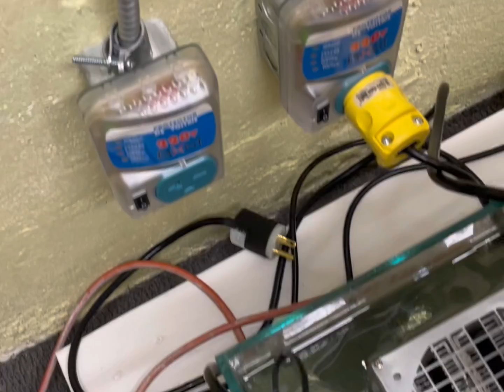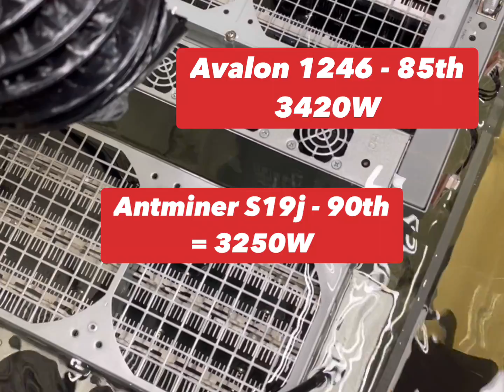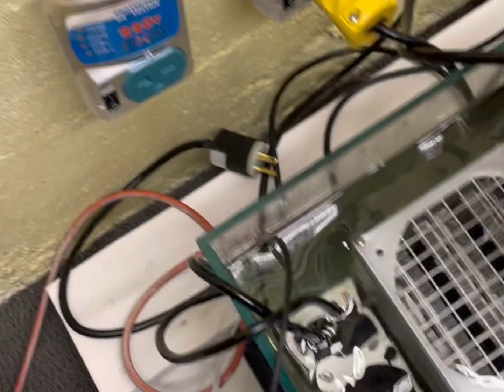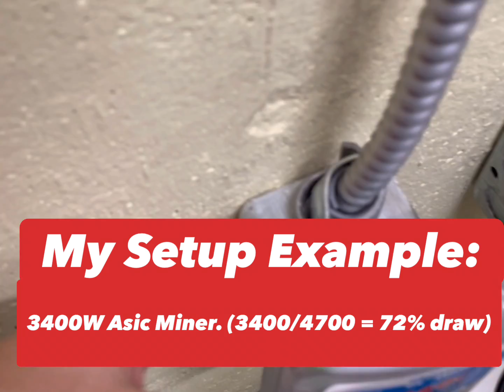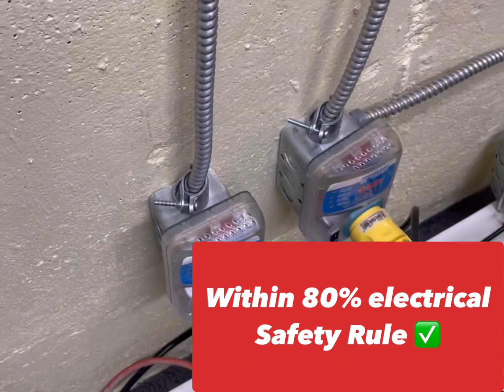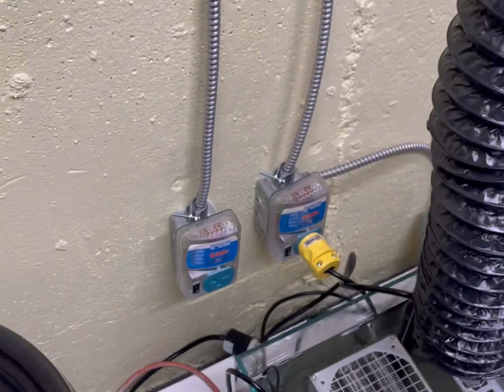Quick rundown: make sure you stay within the 80% rule. These things consume a lot of power. The S19 draws approximately 3100 watts. This is an Avalon 1246, 85 terahash, and it runs a bit more power at about 3400 watts. So when you're wiring your box, make sure you stay within your safe 80% rule. That's basically your amps times your volts, and 80% of that is the safe amount of wattage you can pull from the receptacle.